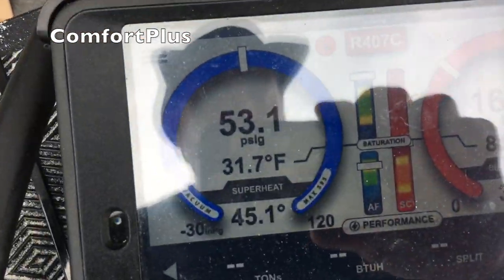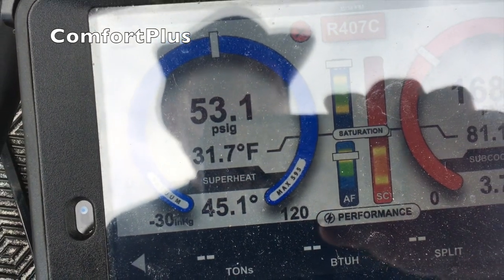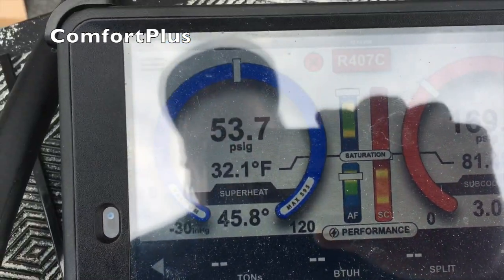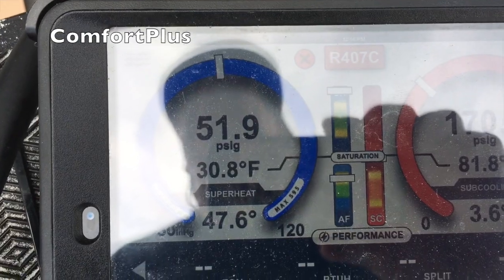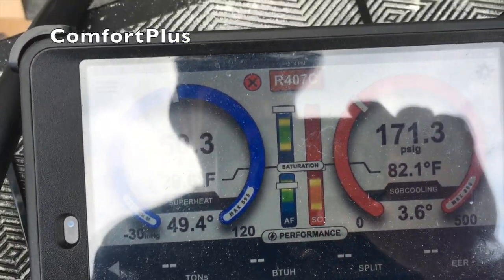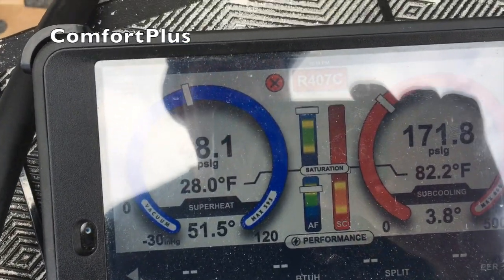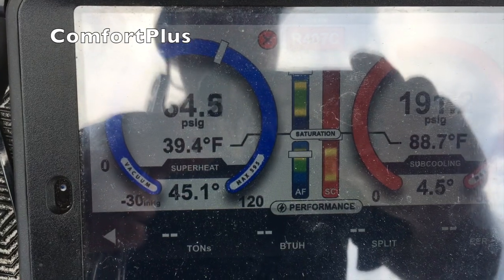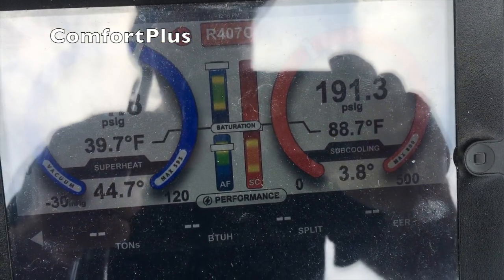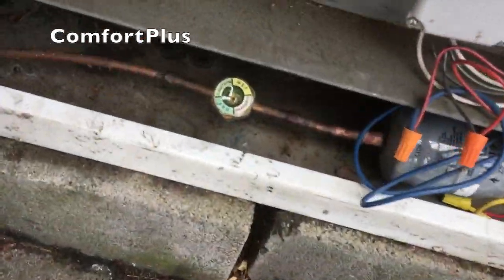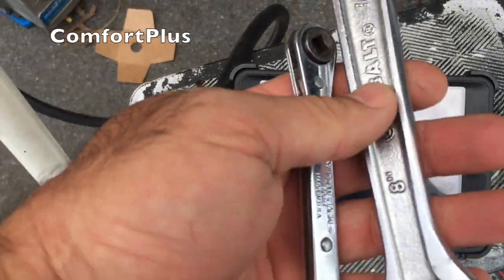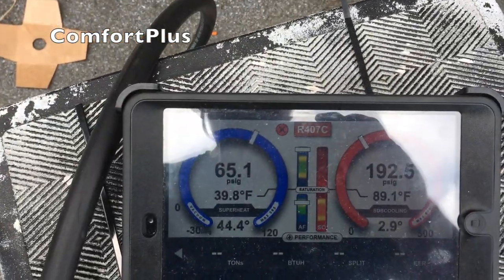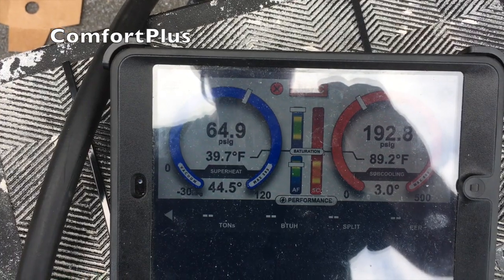How much? 90-degree water right now. Yeah, quieter than the old one. I'd say that old one had been going out for a while. We're running a pretty high superheat. Subcool is only about 3. The sight glass is clearing up, so I'm going to let it run a few more minutes, but I'll be ready to adjust my TXV, bring that superheat down some if needed.